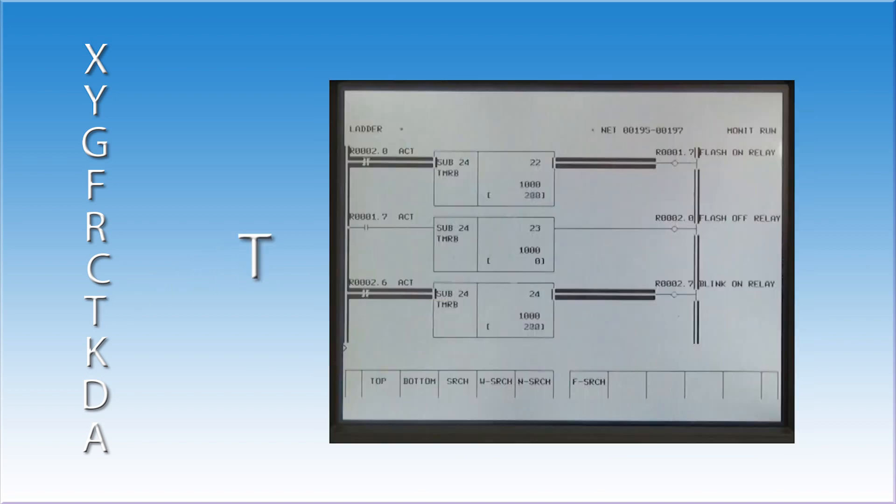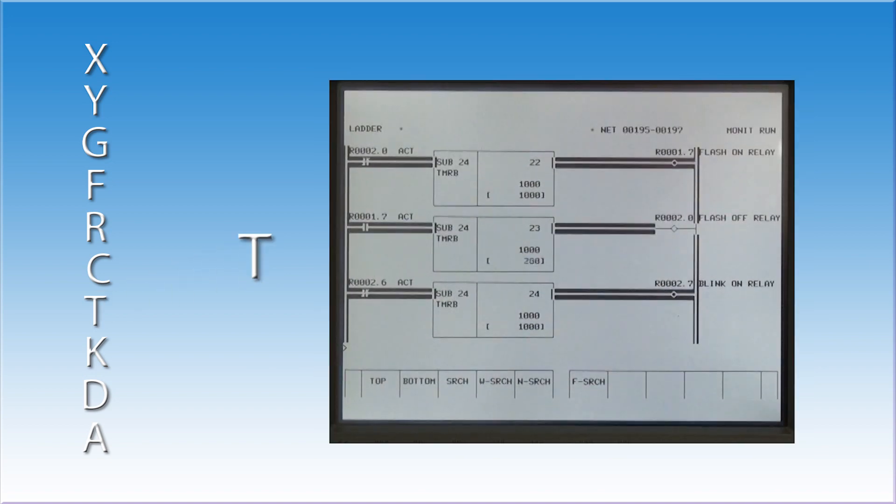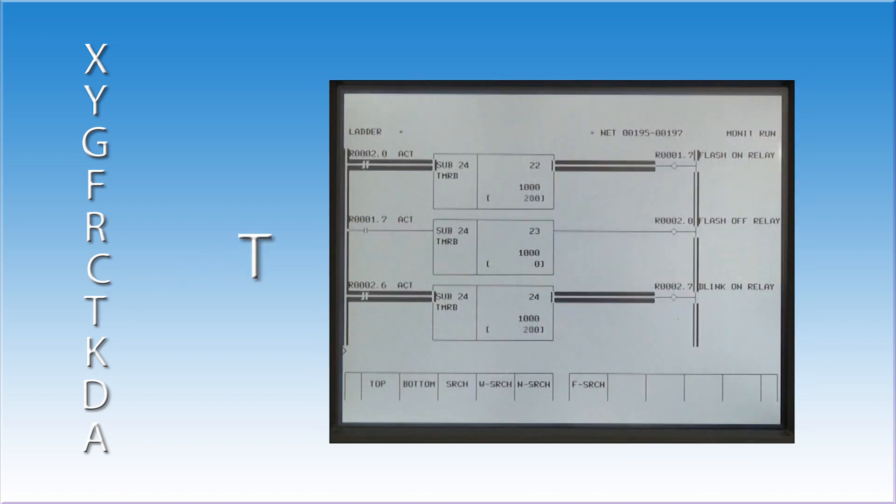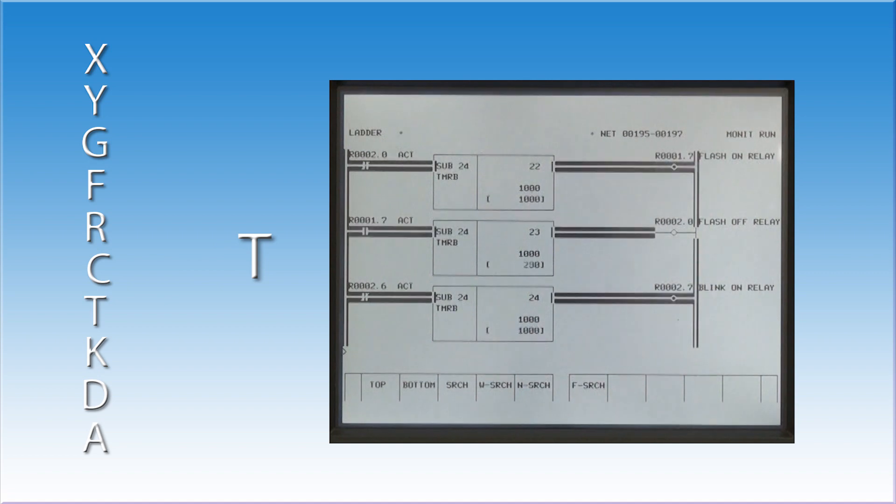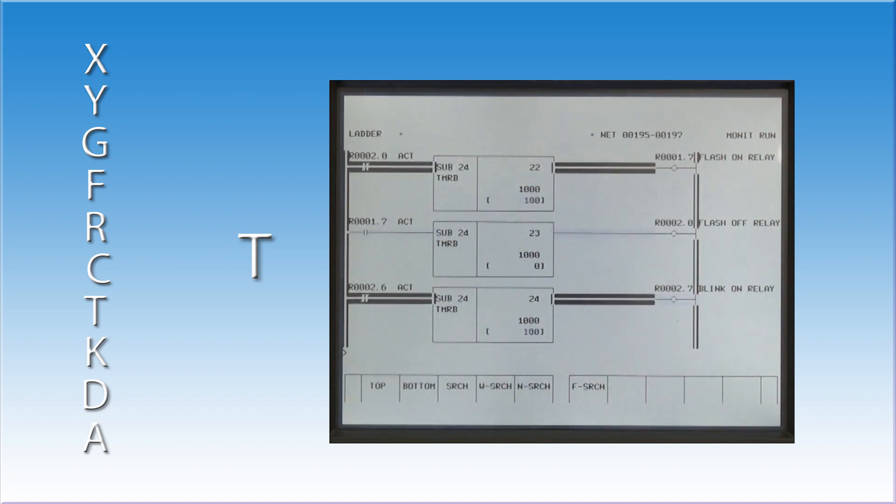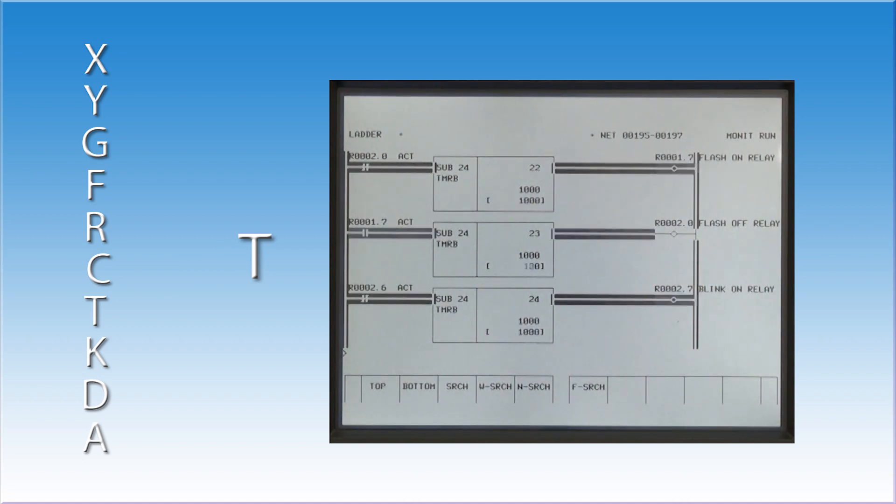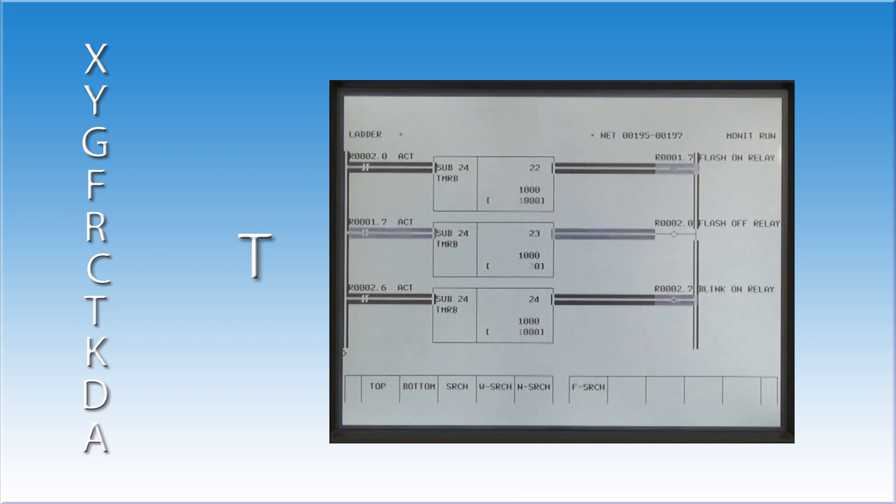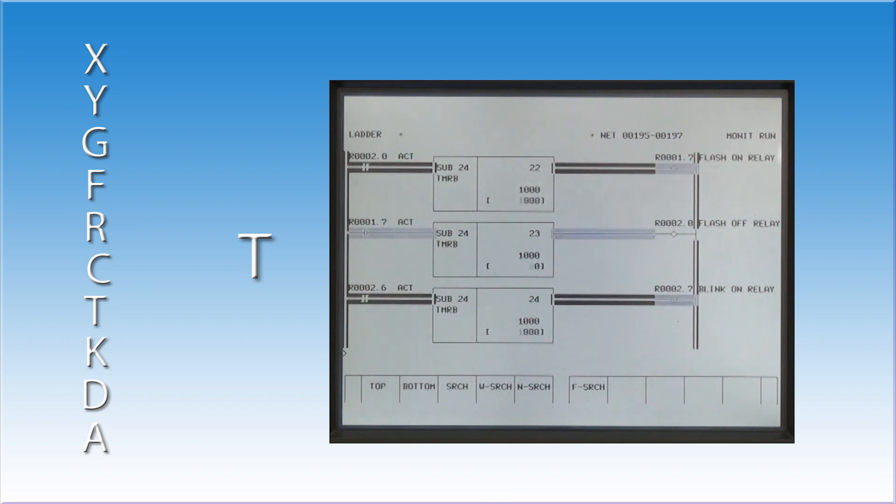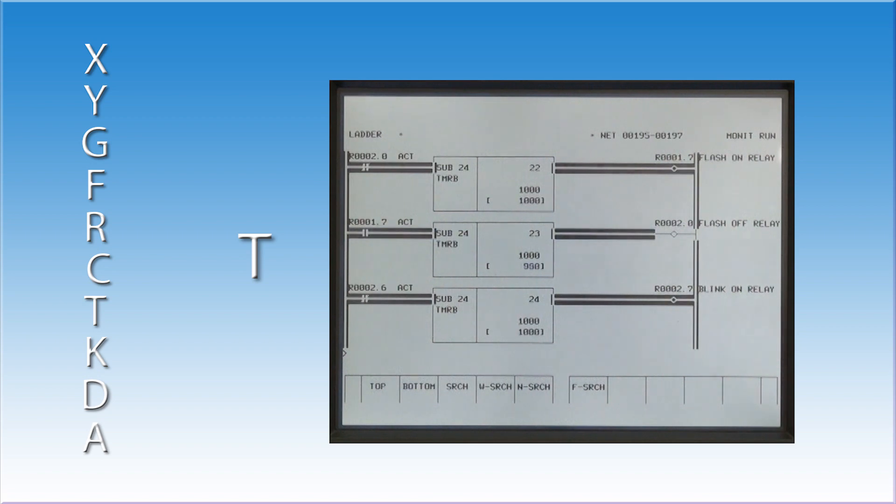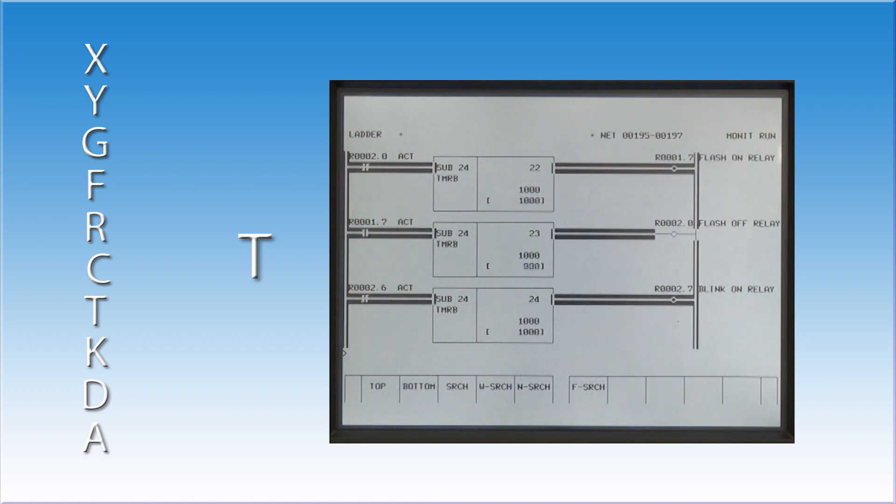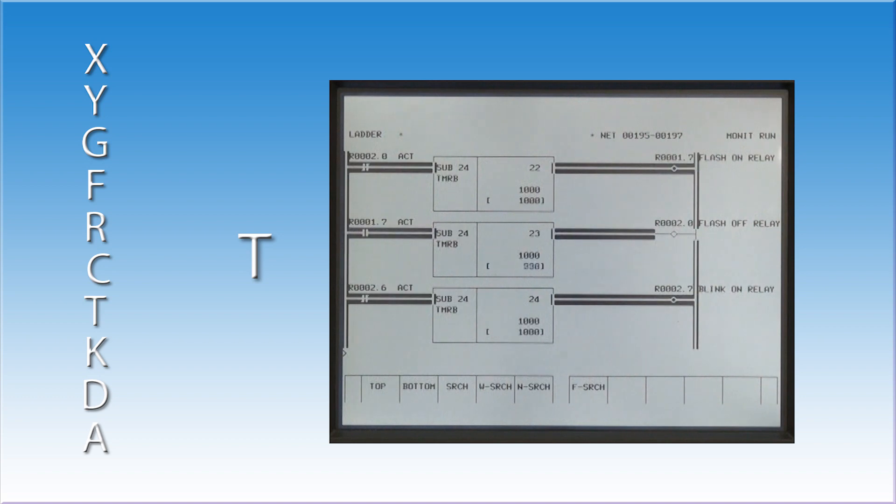The T address is used as a timer. There are several types of timers used in a FANUC ladder. A timer will begin to count up when it is activated. Once it has reached a set value, it will turn on an output. If the timer is deactivated for any reason, it will begin counting from zero when it starts up again. All timers in a FANUC PMC are count up timers.